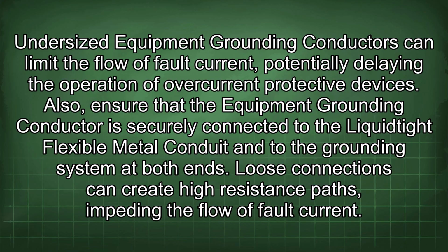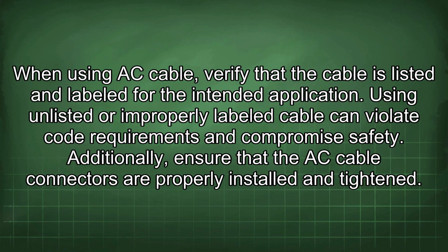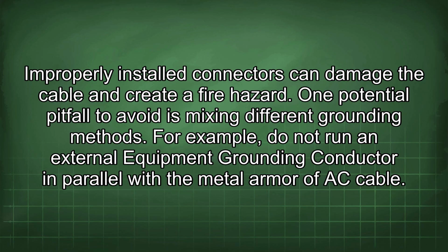Also, ensure that the equipment grounding conductor is securely connected to the liquid-tight flexible metal conduit and to the grounding system at both ends. Loose connections can create high-resistance paths, impeding the flow of fault current. When using AC cable, verify that the cable is listed and labeled for the intended application. Using unlisted or improperly labeled cable can violate code requirements and compromise safety. Additionally, ensure that the AC cable connectors are properly installed and tightened. Improperly installed connectors can damage the cable and create a fire hazard.